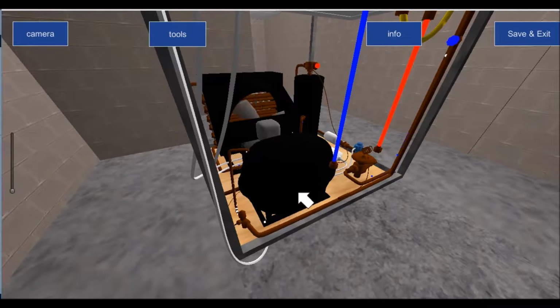I mean, if you were just to take that compressor when it's standing still and give it a shake with your hand, it will rattle, and it's basically the way the actual electrical motor is mounted inside the body, so it's the electrical motor in its casing that's actually rattling against the side walls. So, you know, again, it's only by looking at the specific installation that I could tell you why it's rattling and how to resolve it. But it's not good for these compressors to be on their side or to be lopsided, because that will cause problems with oil circulation and cause the compressor to seize over time.